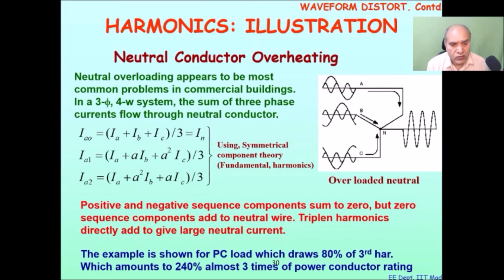See the neutral conductor overheating. For example, if you have data centers where a lot of computers are being used, you know that in computers we use SMPS, a kind of converter which converts AC into different values of DC, and they create third harmonic, fifth harmonic, seventh harmonic, and so on, and most commonly these triplen harmonics. So the harmonics which have multiples of 3 times the frequency of the fundamental. And these triplen harmonics have an interesting property. Rather than getting cancelled, they get summed up because 3 into 120 becomes 360, which is the same as 0 degrees.